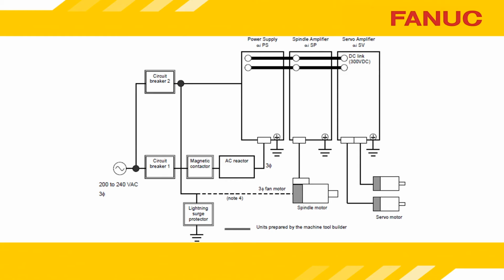An Alarm 5 requires you to look at the big picture. The DC link is created in the power supply module and shared among all the amplifiers that are connected to it. If one amplifier says the DC link is low, all of its friends should be saying the same thing. The spindle amplifier's alarm for DC link undervoltage is 51 and the power supply module's is 4. So with everybody watching the voltage on the DC link, if you only have a single unit claiming it is low, take a really hard look at that one unit.